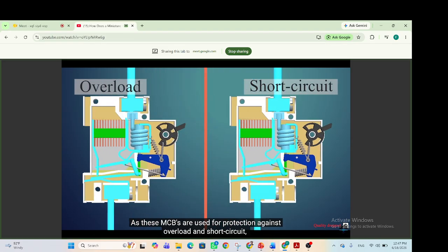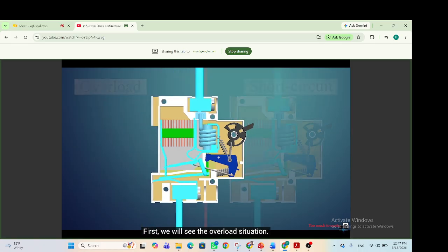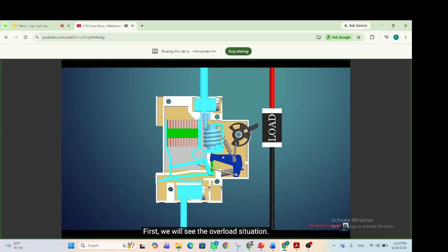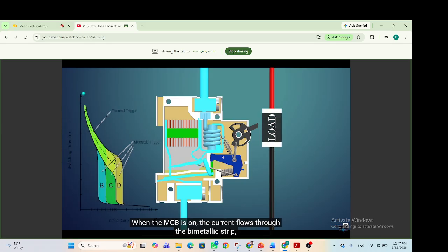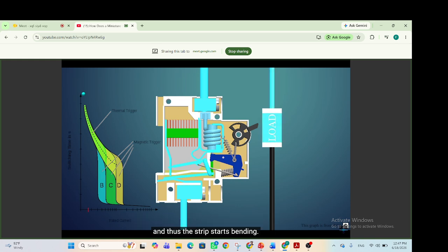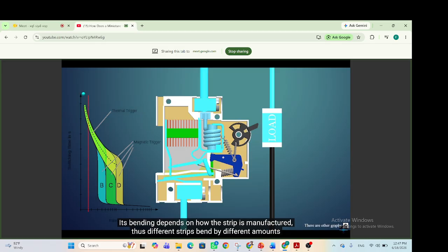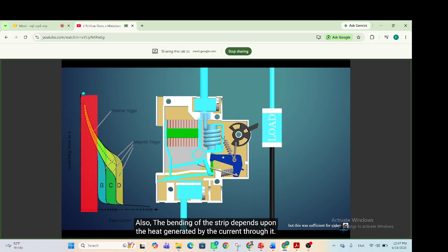As these MCBs are used for protection against overload and short circuit, let us look at both cases. First, the overload situation. When the MCB is on, current flows through the bimetallic strip, and the strip starts bending. Its bending depends on how the strip is manufactured, so different strips bend by different amounts for the same current. Also, the bending depends upon the heat generated by the current through it.